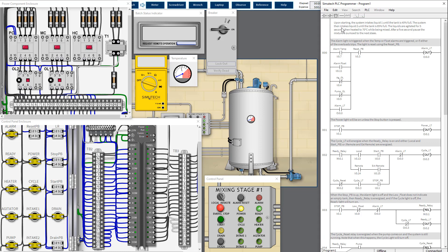Program 1 description states: the system intakes liquid one until the tank is 40 percent full, then intakes liquid two until the tank is 85 percent full. The liquids are agitated for five seconds then heated to 70 degrees while being mixed. After a five second pause the mixture is pumped to the next stage. This is not the correct one either because the mixture does not pump out in five bursts, so we still need to change to another program.